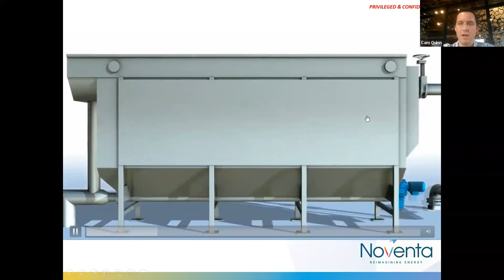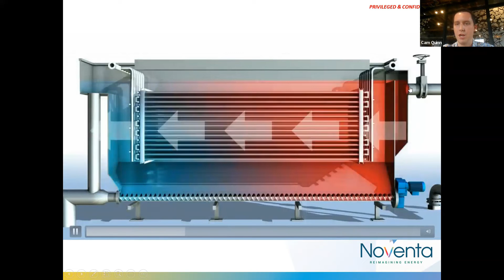This is what I would call a modified shell and tube heat exchanger. We're going to see the inside of it in a second. On the shell side, we have wastewater coming in, getting heated up or cooled down, and then flowing by gravity out the bottom. On the tube side, we have either the condenser or the evaporator loop of the heat pump or chiller connected to it. And over time, as I said, there's going to be biofilm growth and sediment deposit on the tube.